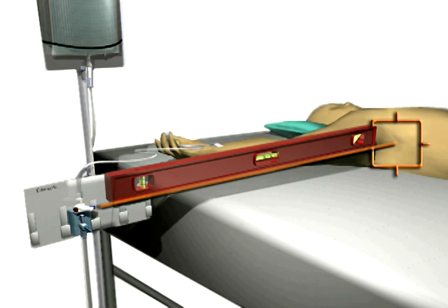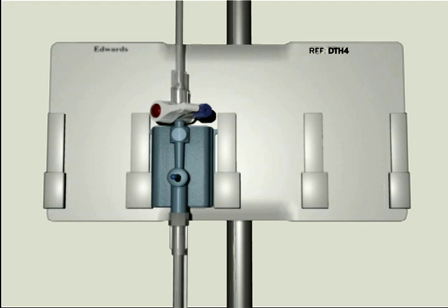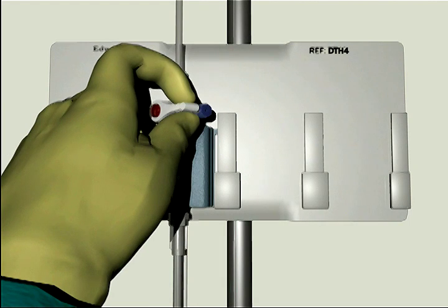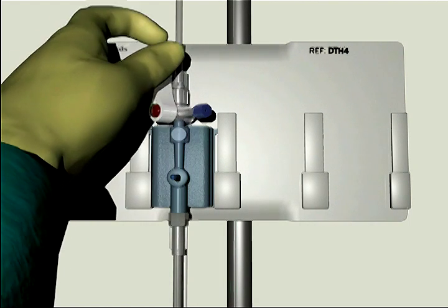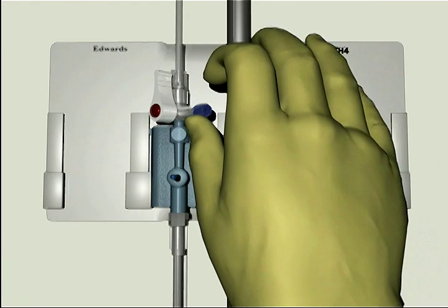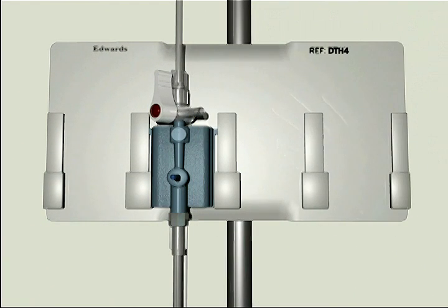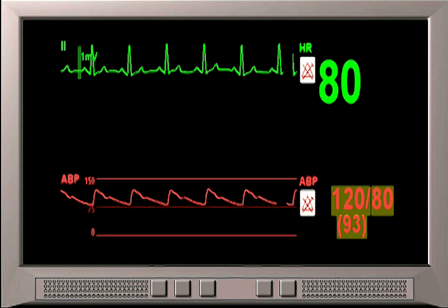Note: it's important to maintain the level of the transducer with the phlebostatic axis at all times while monitoring to ensure accurate pressure readings. The TruWave transducer must be zeroed to remove the effects of atmospheric pressure. Step 3. Open the stopcock above the transducer to atmospheric air by turning the stopcock toward the patient's pressure tubing and away from the TruWave transducer, then remove the non-vented cap. Perform this maneuver while maintaining sterility of the cap and stopcock port.